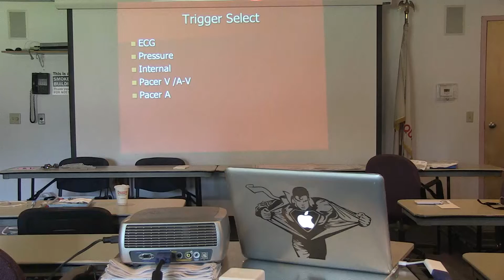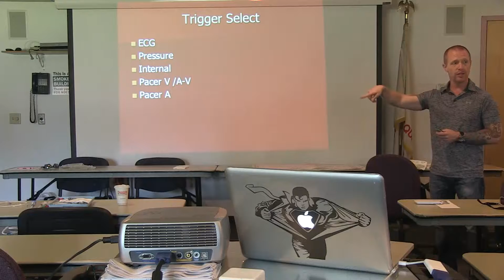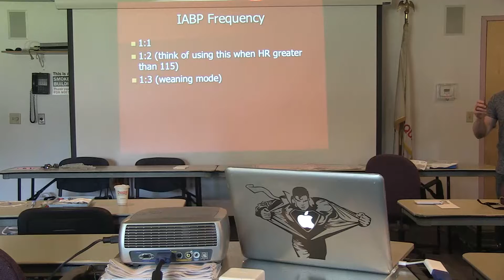Okay? So we talk about augmented pressures and things like that too. So let's get into that. With trigger select, you can set the trigger based on what the ECG tells you. You can look at your ECG strip and say, I want to set the trigger based on this. You can set it at pressure, you can set it internal, you can set it on the pacer, you can set it however you want. But 1 to 1 means every time your heart pumps, one balloon inflation. This is the one that we use most frequently for transport.